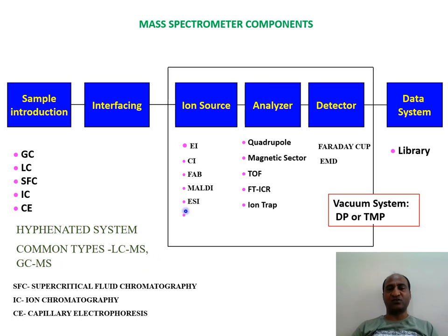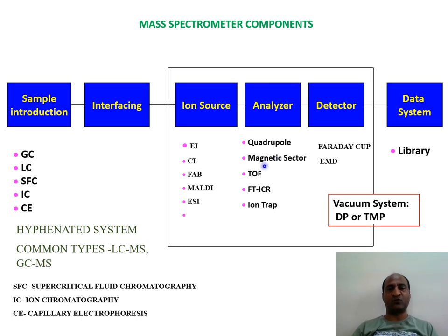The ionization techniques include electron impact, chemical ionization, FAB (fast atom bombardment), MALDI, and ESI (electrospray ionization). The analyzer types include quadrupole, magnetic sector, time of flight, Fourier transform, ion cyclotron resonance, and ion trap. These two systems — ionization and analyzer — can be combined in various ways to get different types of mass spectrometers. For example, electron impact with magnetic sector, electron impact with time of flight, chemical ionization with quadrupole, or chemical ionization with magnetic sector. This gives a wide variety of mass instruments that we can use based on our needs.